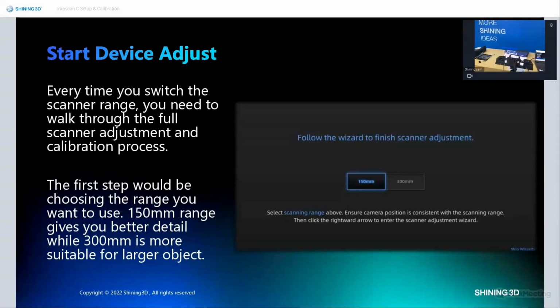Now, that's all for the talking, and we can start the device adjustment. First, I want to talk about when to do the device adjustment. Every time you switch the scanner range, you need to walk through the full scanner adjustment and calibration process. And the first step for this would be choosing the range you want to use.